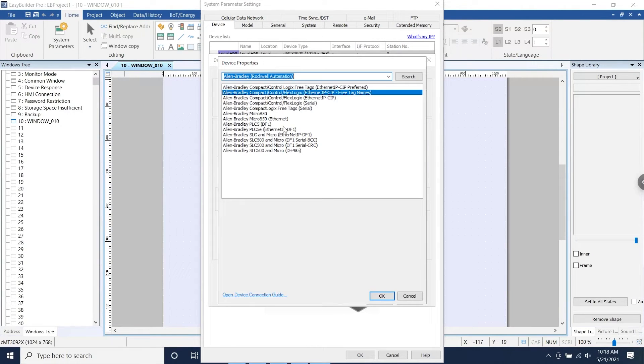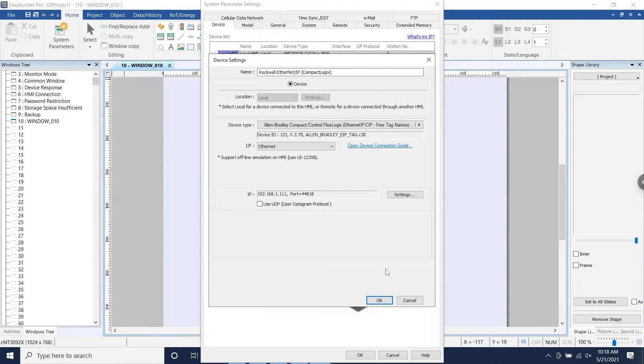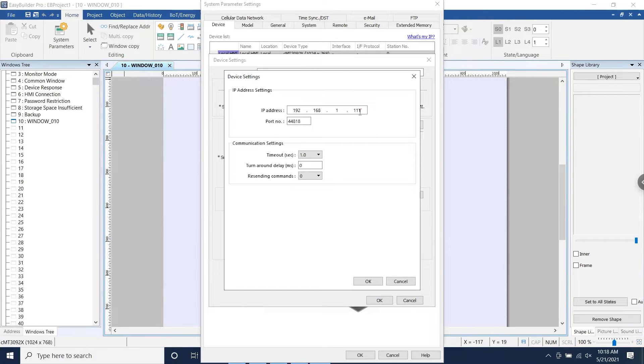In the following menu, next to Device Type, I'll select the drop-down list and then search for our Allen Bradley Compact Logix driver. I'm going to select the Allen Bradley Compact Logix free tag name driver. Then, with our driver selected, I'm going to configure the IP of my device by selecting the Settings button. Once finished, I'll click OK and return to the Device tab of our System Parameters.